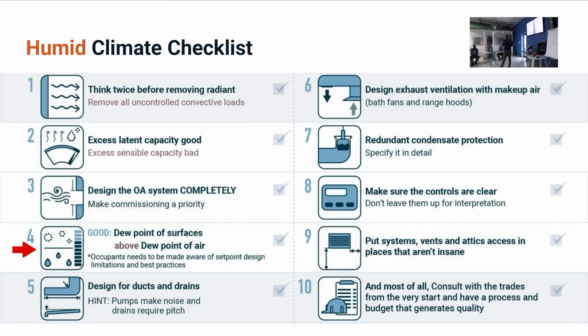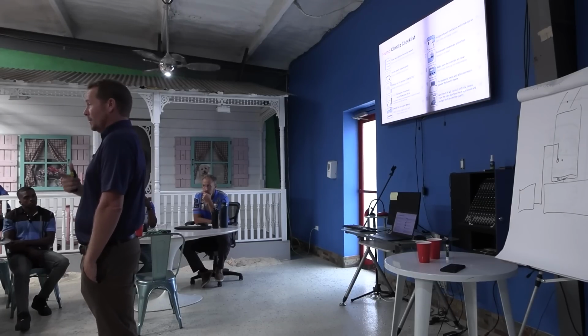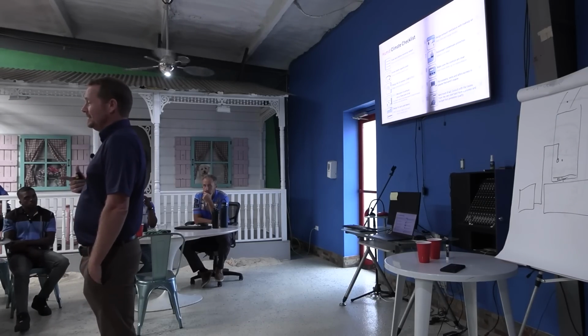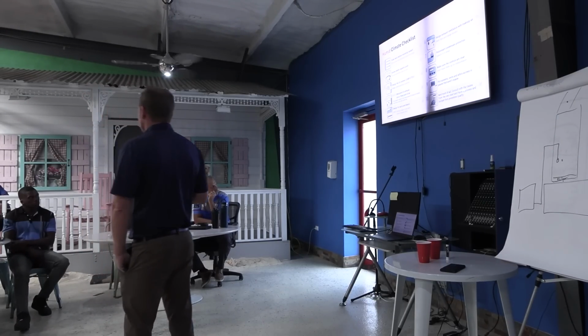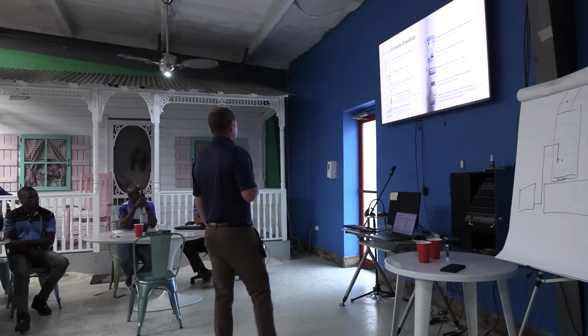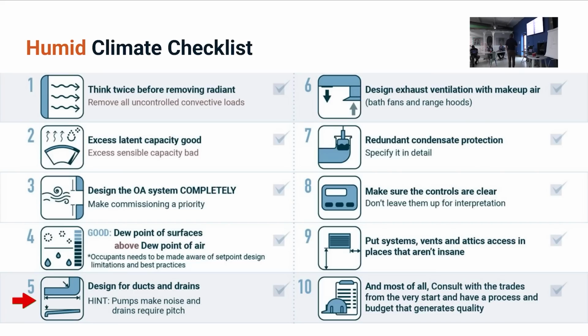Good: keep the dew point of surfaces above the dew point of the air. That's what we want—surfaces warmer than the dew point of the air. Anytime you wonder why something's sweating, it's because it's colder than the dew point of the air around it. Full stop, that's the whole reason, always. So what are your choices? You can warm it up, or you can decrease the dew point of the air around it. Those are the only two things you can do, and that's what you want to think about how to accomplish.